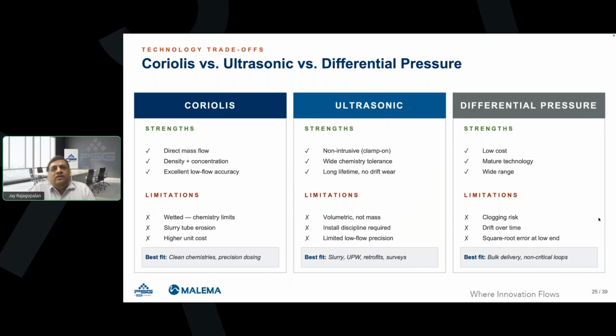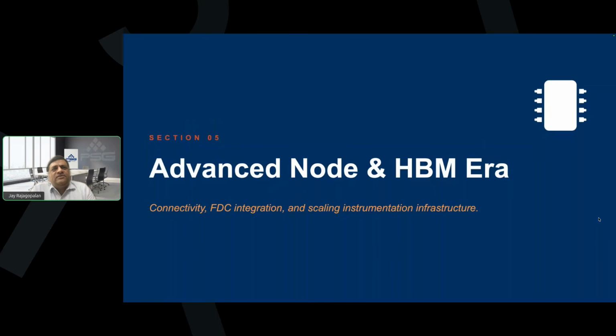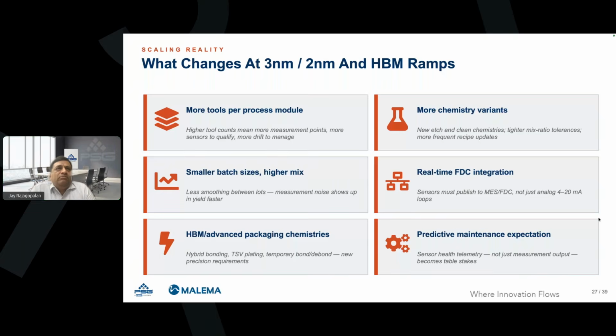Let's move on to what are the demands for the high bandwidth memory, as well as advanced nodes, especially from the connectivity standpoint. Just the flow meter measuring flow and outputting flow as one variable, is it sufficient? What are the other requirements? What changes in these advanced nodes? More tools per process module. Obviously, extremely higher number of data points, measurement points. More chemistry variants, obviously, the different mixers, different recipe changes occur frequently. Smaller batch sizes and higher mix. So that is also a critical point to note.